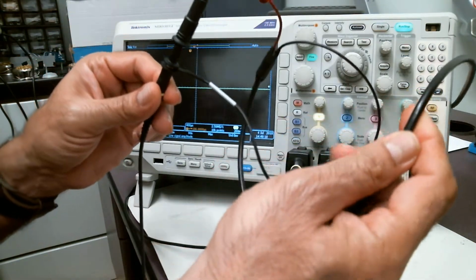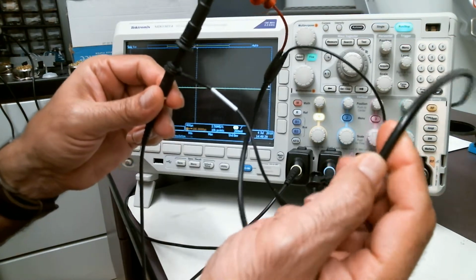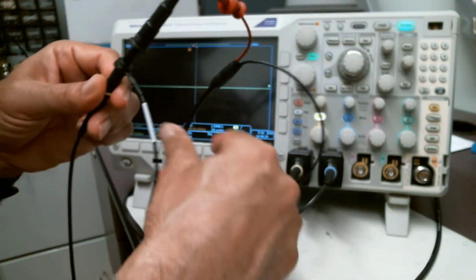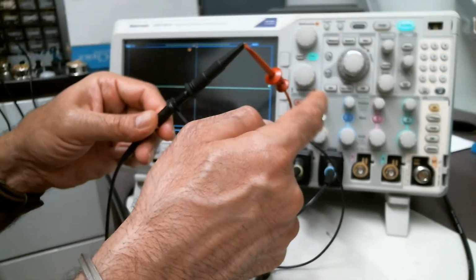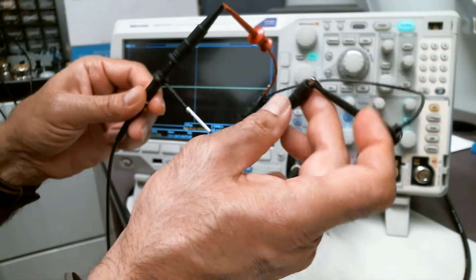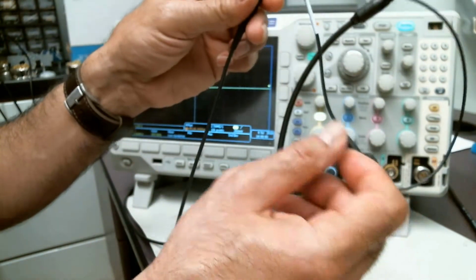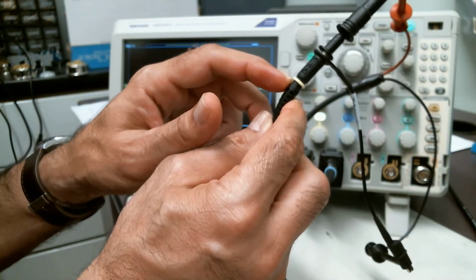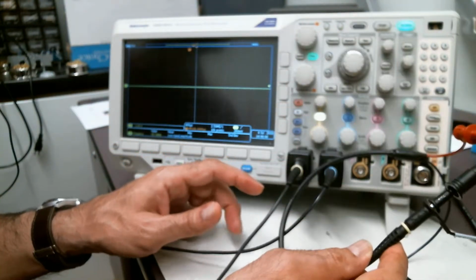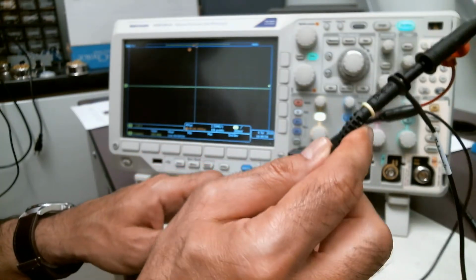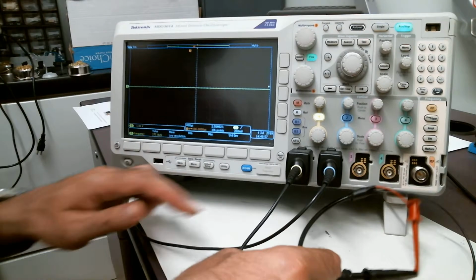So this is a BNC cable coming from the back, connected to the AFG connector. And this red wire here on this BNC cable is bringing the signal from the AFG, whereas this black connector is bringing the ground. So I have connected it. I'm going to check these signals, set them up on channel number 1, which is the yellow channel, and as you can see here, I have a yellow ring. So that's where it is connected. So you can monitor it on channel 1 and configure and change it.